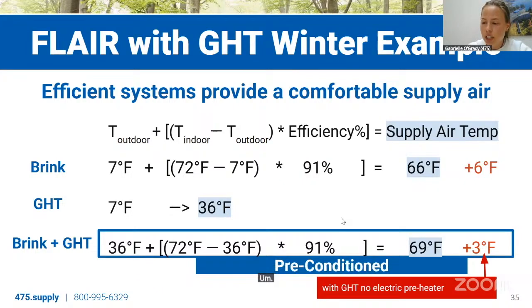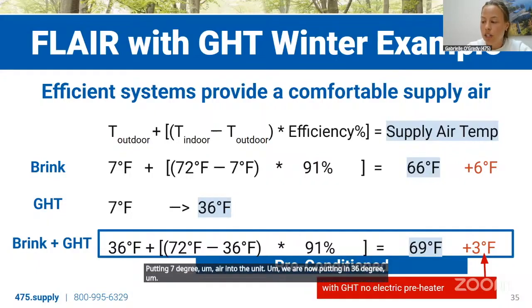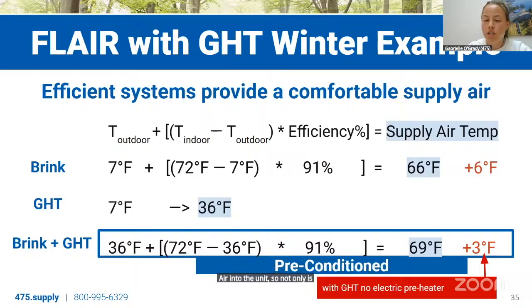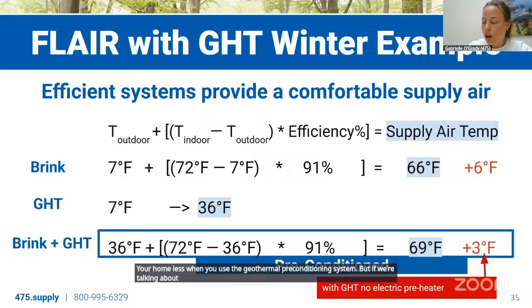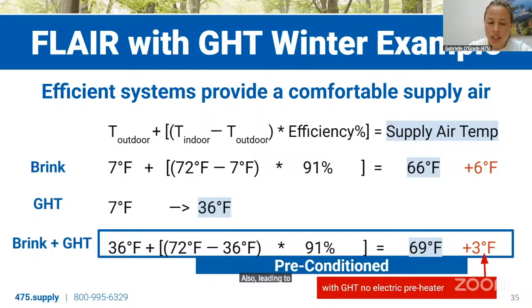And then we can see what the GHT can do. Instead of putting 7 degree air into the unit, we are now putting in 36 degree air into the unit. So not only is the supply air temperature going to rise, meaning you're going to have to heat and cool your home less, but in winter you are also not going to have to use the included electric preheater as much, also leading to additional savings.